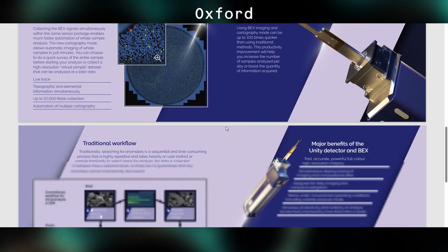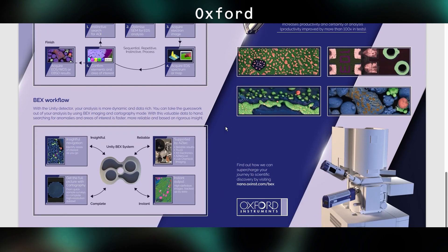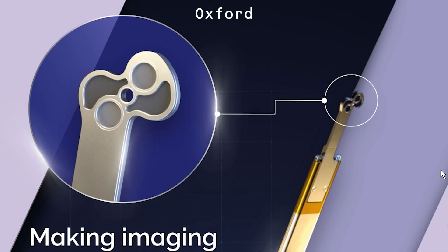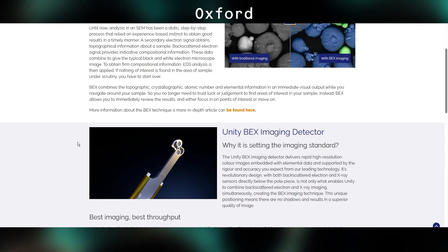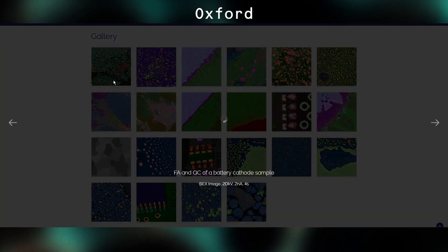What numbers can I give you on this? It is very new, so their brochure is properly vague about everything — nothing states the detector sizes, count rate, energy resolution, or anything — but I was able to get a few details at the show. Because there are two BSE segments, you can view the sample in topo mode by turning one of them off. Both EDS detectors have filters on them but are limited to 20 kV. It can operate in low vacuum or with a cryo stage. The head section on its own is replaceable if it gets damaged, which is good. The funny shape of the head has a dip in the top so a normal EDS detector can fit in there and operate with it at the same time. Just the detector with no software, they said at the show, would cost around 35,000 to 40,000 euros, which is about 35,000 to 40,000 US dollars.